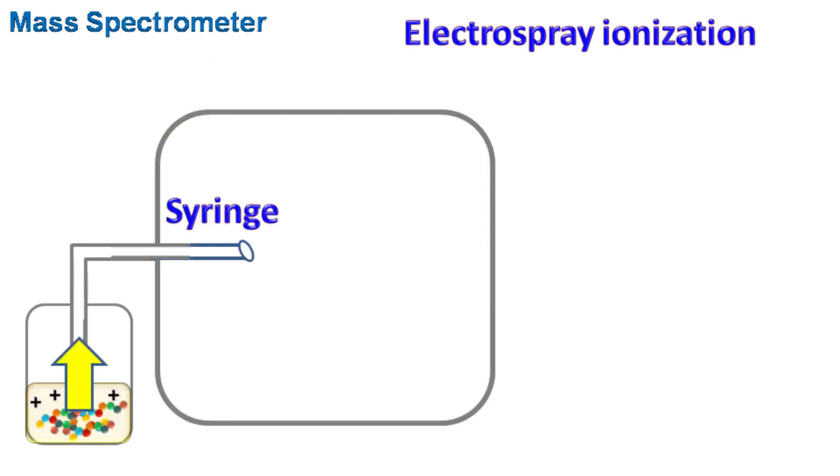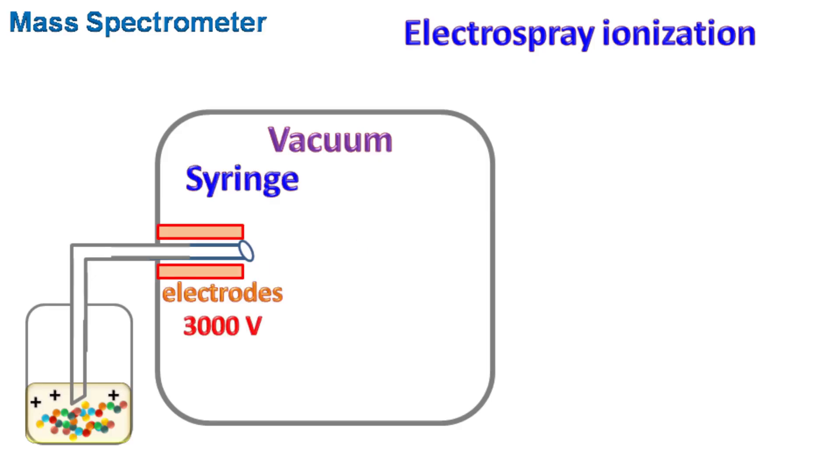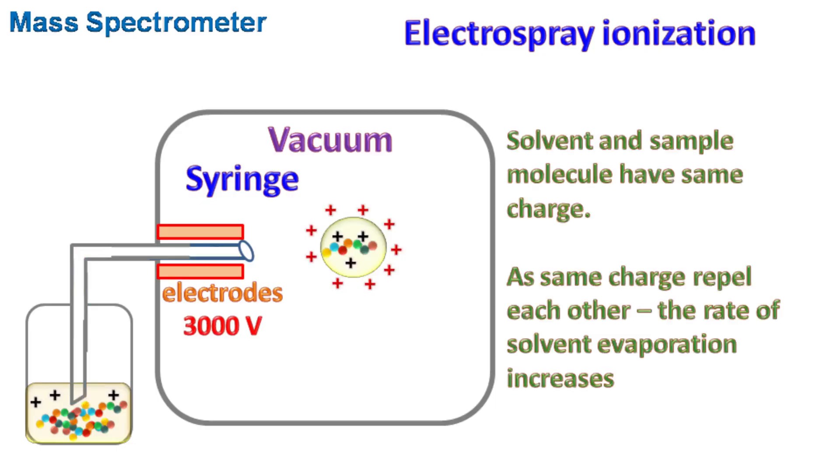This solution having charged molecules is passed through a syringe to create an aerosol. This process is known as nebulization. Because of vacuum in the chamber, the solvent molecules evaporate, leaving the charged molecule to enter the analyzer. To increase the rate of solvent evaporation, a strong potential difference of about 3000 volts is applied at the end of syringe. This makes the solvent molecules electrically charged. As the solvent molecules and the sample molecules have same charge, the rate of evaporation increases as both the charges repel each other.